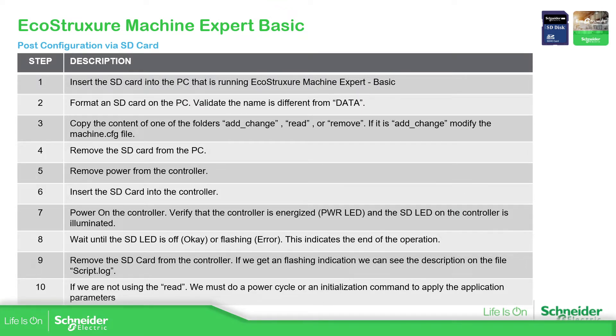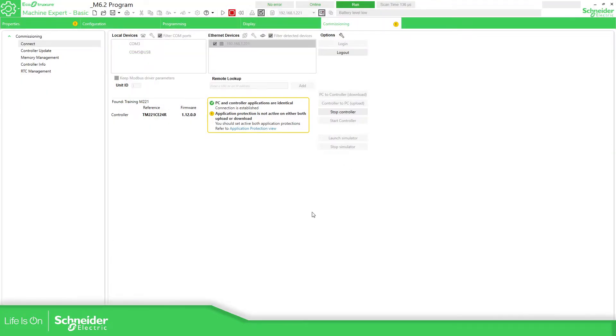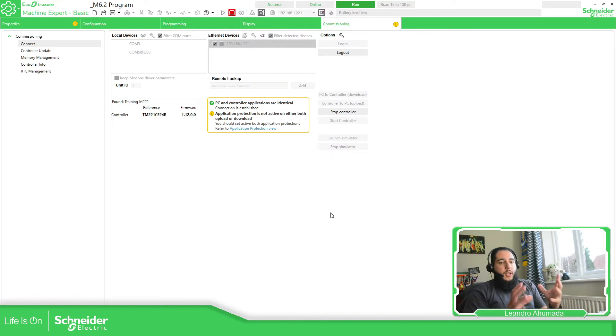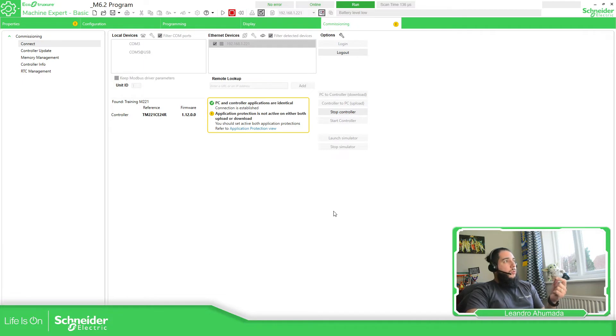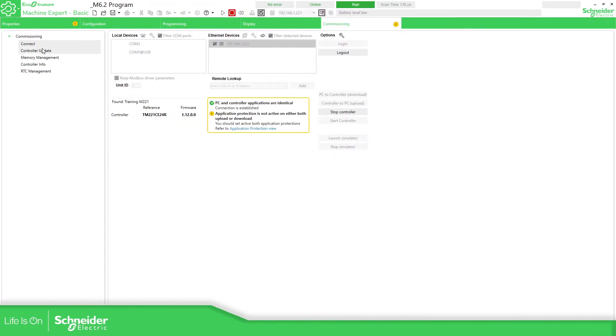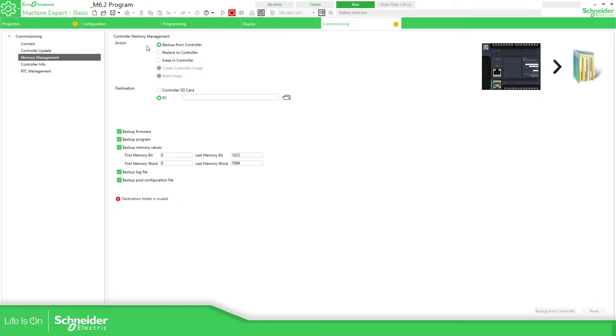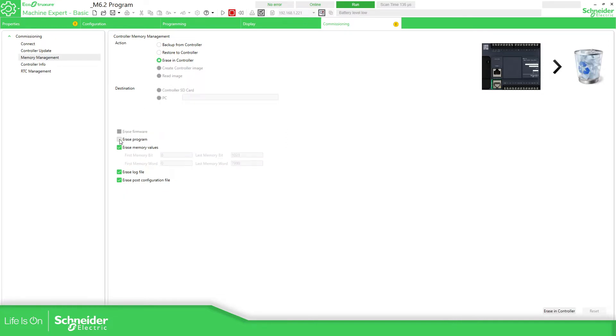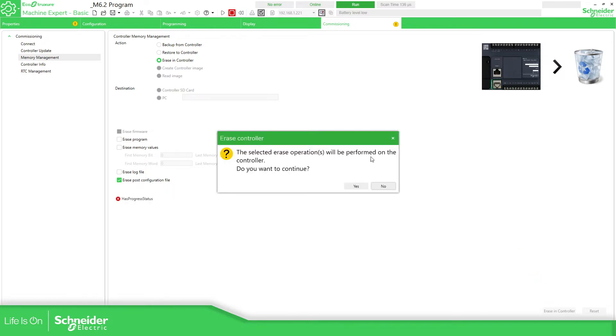If you are directly connected to the PLC and want to change the configuration without using the SD card, that's also possible. First, connect with the controller. Then go to memory management, where you have options when online: Backup, Restore, and Erase. What you need to do is 'Erase in Controller' — in our case, only the post configuration files. Select it and confirm.